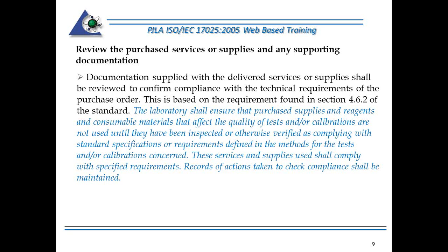Those of you who issue calibration certificates from your laboratory, as opposed to test reports, are aware of the complexity of information that has to be on the certificate. Test reports are equally as complex, but they contain a slightly different set of information. They address information that is provided in a slightly different way. For instance, with regard to measurement uncertainty on a calibration certificate and measurement uncertainty on a test report.